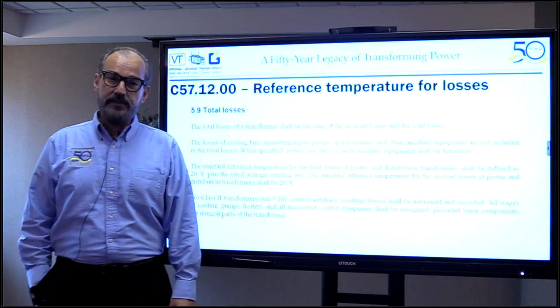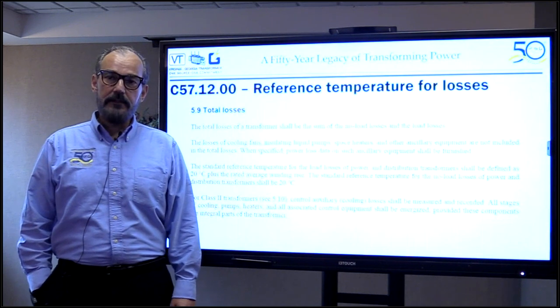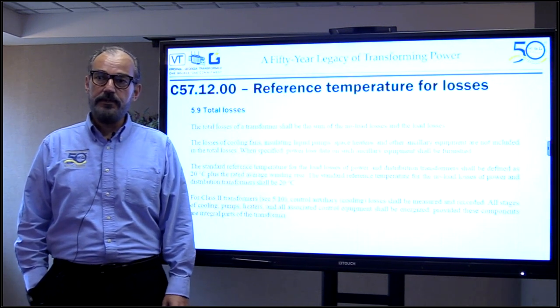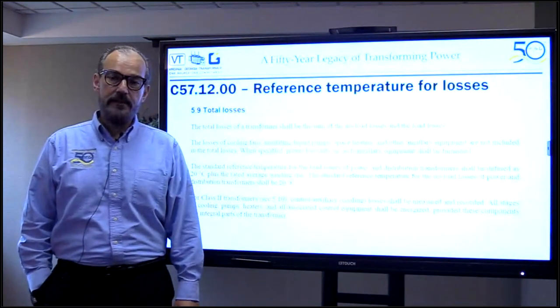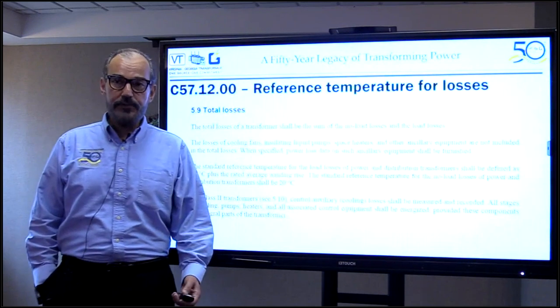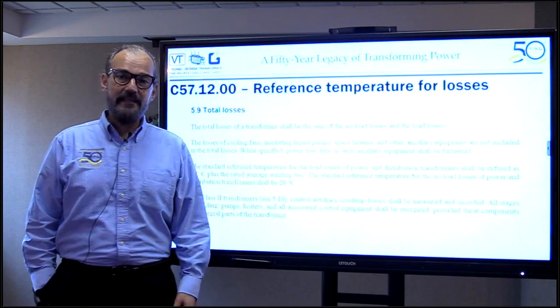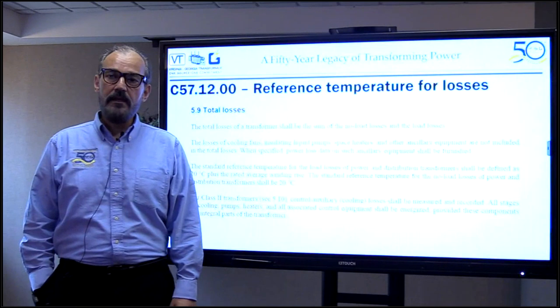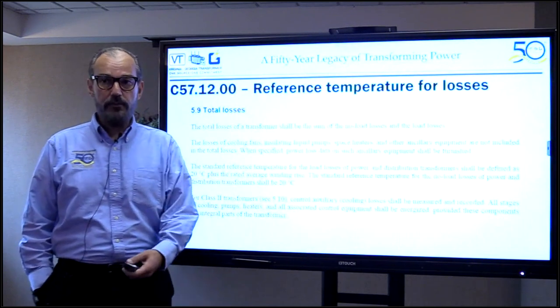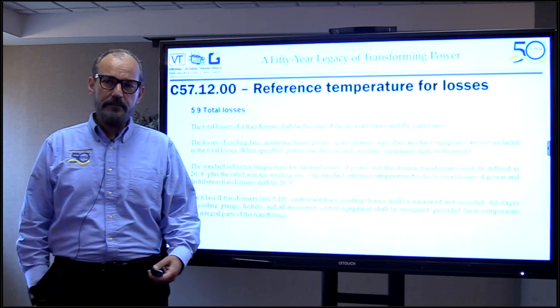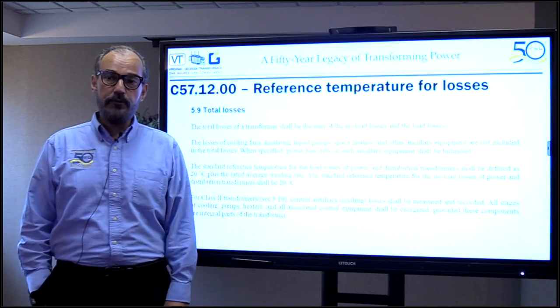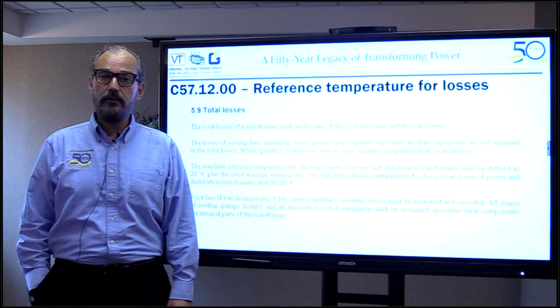I want to start with the reference temperature for losses. The standard reference temperature for losses of power and distribution transformers shall be defined as 20°C plus the rated average winding rise. So if your transformer's average winding rise is 65°C, the losses we report must be reported at 85°C. Temperature rise during operation is one of the critical parameters used for several tests and test reporting that all manufacturers must follow.